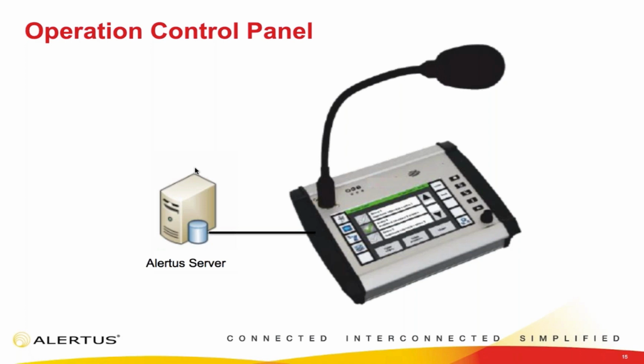This device usually sits in the emergency operations center, or with your police, or, for some of our K through 12 customers, it may be in the principal's office or dean's office. Some of the chemical and refinery customers, and also government, require multiple operation control panels, which we can do. It is smart to have one operation control panel in your main emergency operations center, and one in a completely geographically distinct area on the other side of the facility. So let's say you have a chemical release and you need to scramble out of the primary location, you can now activate from the other facility.